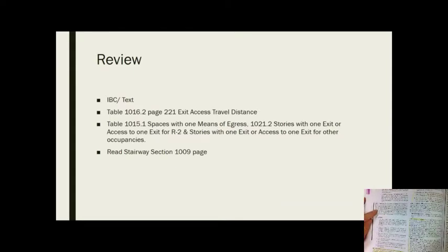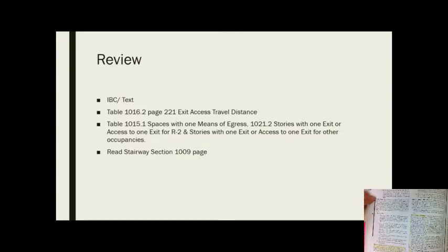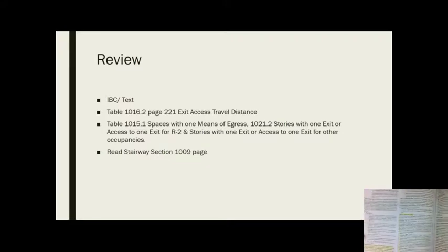This is a very important chapter here. You'll notice that I have it underlined, so you need to make sure you mark 1009.3 stairways. And it's going to give you exceptions. The clear width of 48 inches between handrails is not required in buildings equipped with an automatic sprinkler system. It's telling you how big it is and what the exceptions are.